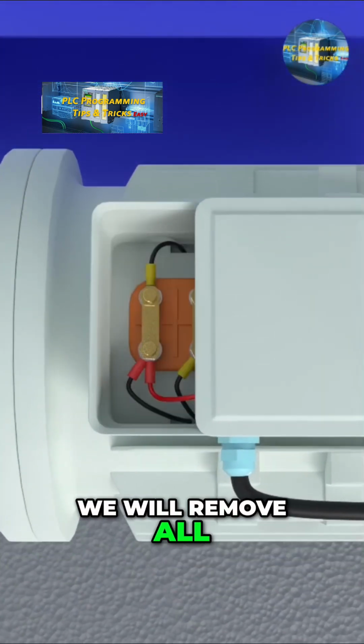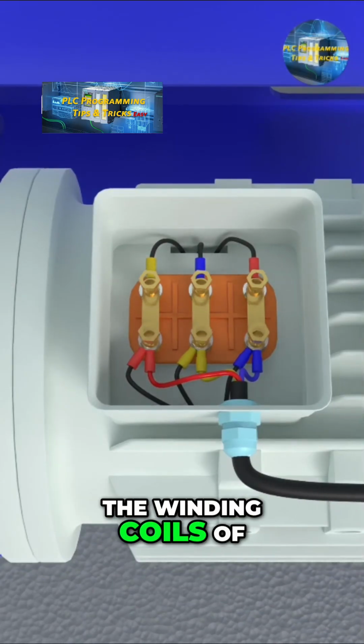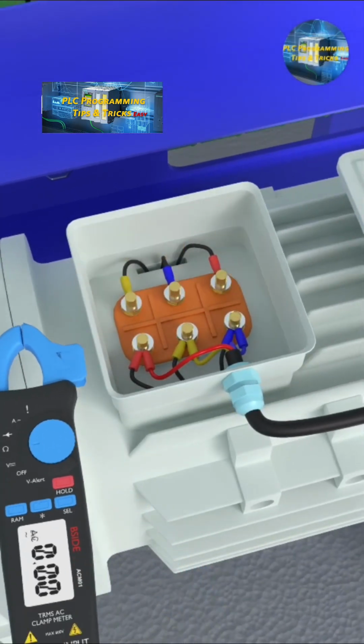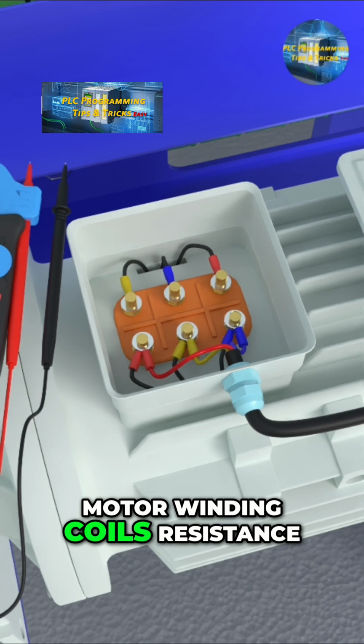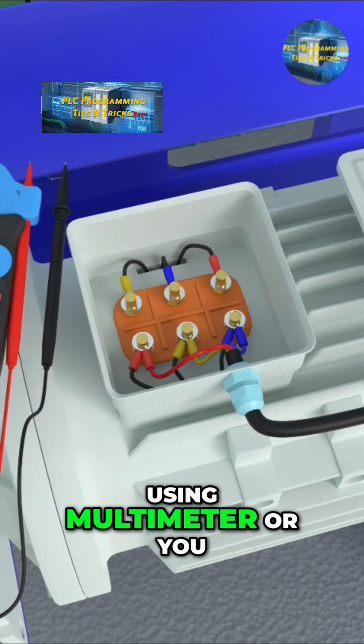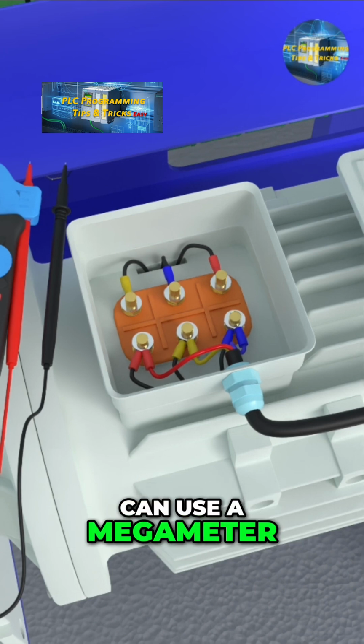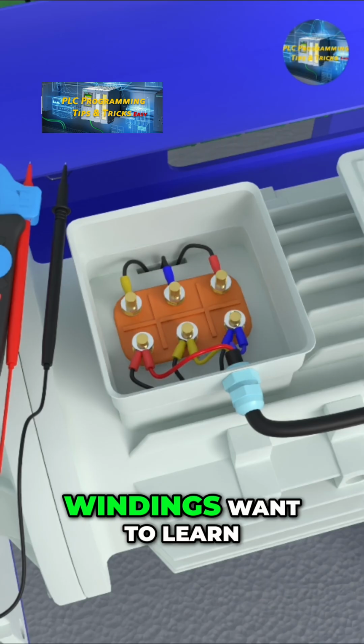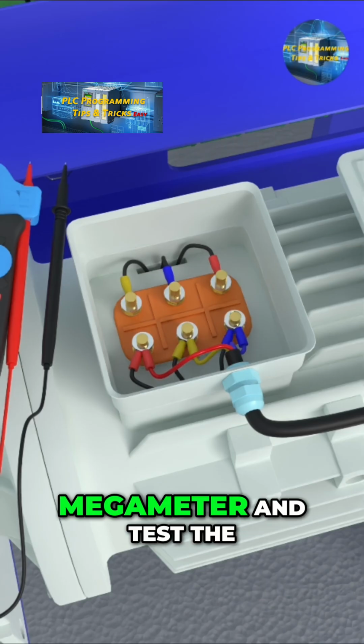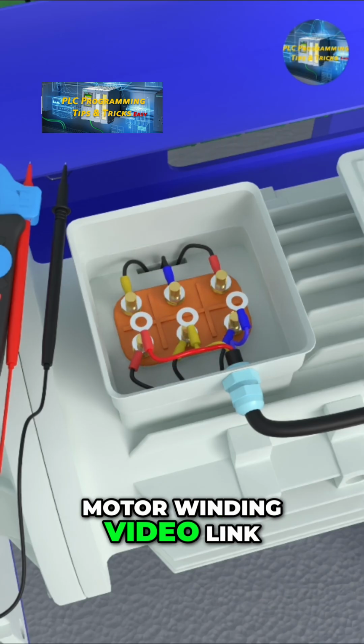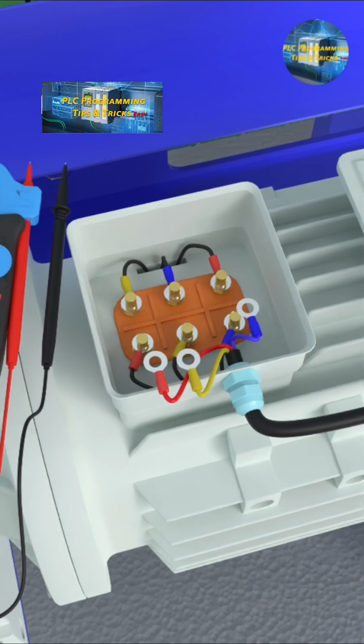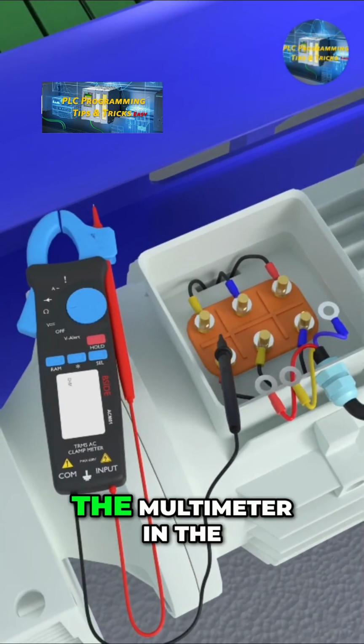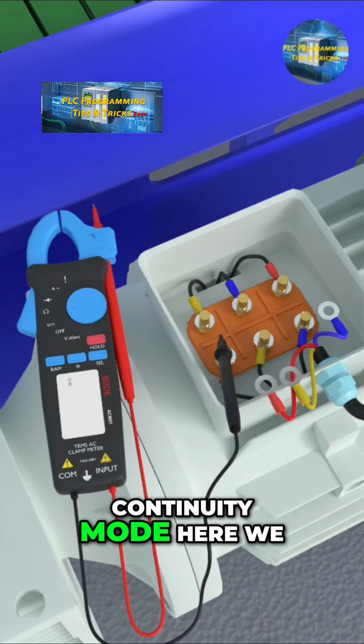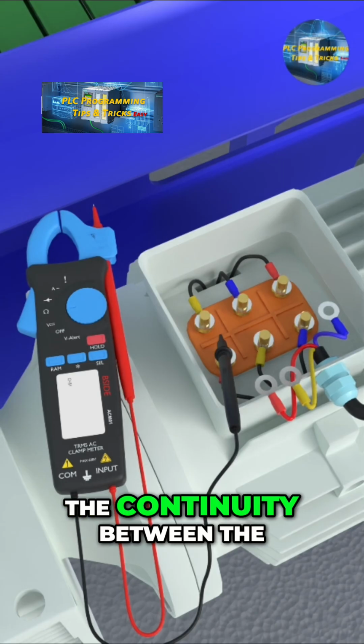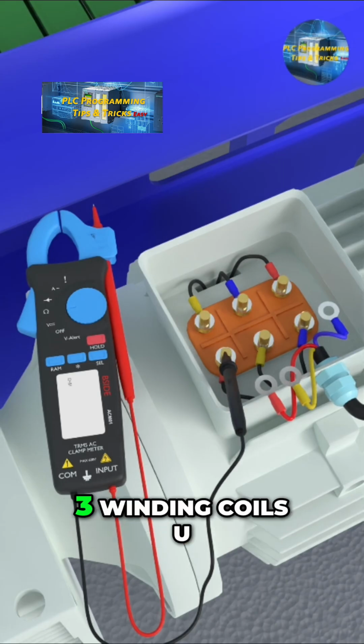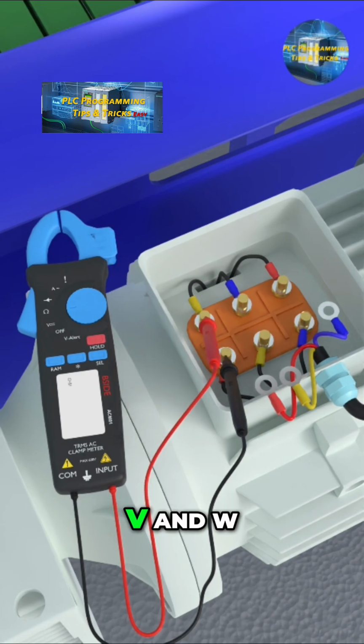We will remove all the connections and test the winding coils of the motor. We can test the motor winding coil resistance using a multimeter, or you can use a megohmmeter to test the motor windings. Want to learn how to use a megohmmeter and test the motor winding? Video link is in the description box. First, we will set the multimeter in continuity mode. Here we will try to check the continuity between the ends of all three winding coils, U, V and W.